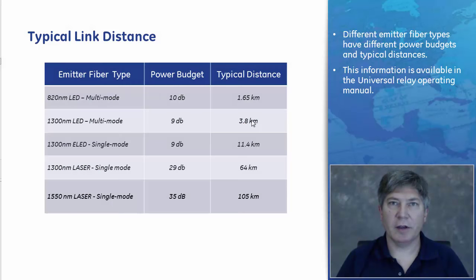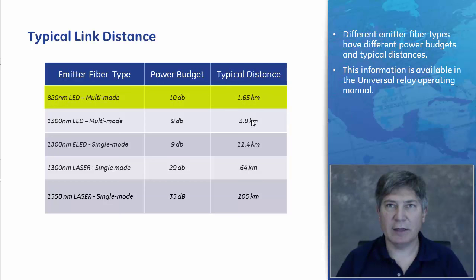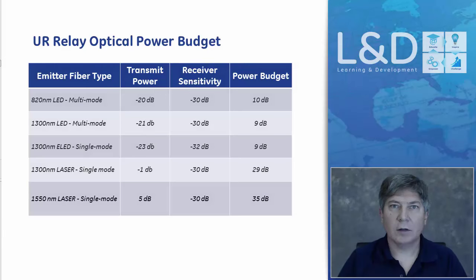This table from the UR manual outlines typical link distances based on emitter fiber type, showing different light sources, their associated mode types, power budgets, and typical distances. For example, an 820 nm LED in multi-mode has a 10 dB power budget and will operate for a typical distance of 1.65 km. At the bottom of the table, the 1550 nm laser light source in single mode has a power budget of 35 dBs and a typical distance of 105 km. A second table outlines the optical power budget for each emitter fiber type, including transmitting power, receiver sensitivity, and power budget.